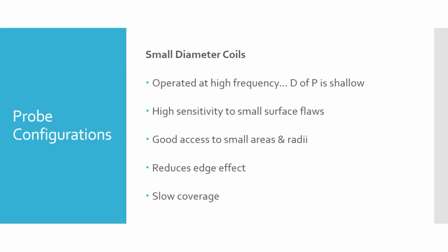Smaller probes also reduce something called edge effect - as the probe gets near the edge of a component, it changes the inductive reactance, because there's less material underneath the face of the coil near the edge. If we have a piece of material and put our probe on the surface, the magnetic field doesn't go just straight down, it spreads a little. As we move the probe toward the side, a portion of that field - those flux lines - spreads out, so there's less material generating eddy currents underneath the face of the probe, and the inductive reactance changes. You'll get a different reading in the middle than near the edge. But the smaller the diameter of the probe, the less this field spreads out - it's more focused underneath the probe, which can reduce that edge effect.